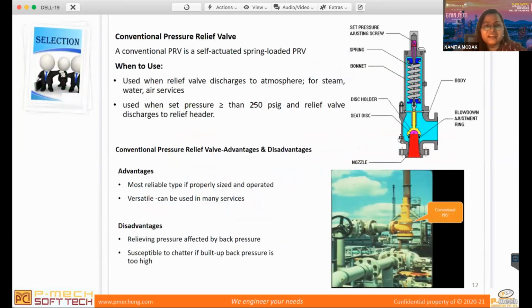So this is a typical conventional pressure relief valve. As I said, when the back pressure to set pressure ratio is less than 10%, then you go with this type of valve. If you see the advantages, it's the most reliable type if properly sized and operated. Versatile, it can be used in many services. It is used in places where it is open to atmosphere, in most cases for steam, water, and air services. And the disadvantage is that the relieving pressure is affected by back pressure, because of this spring which is set here. So it is normally affected by the back pressure which this PSV is experiencing. So it is highly sensitive to the back pressure.